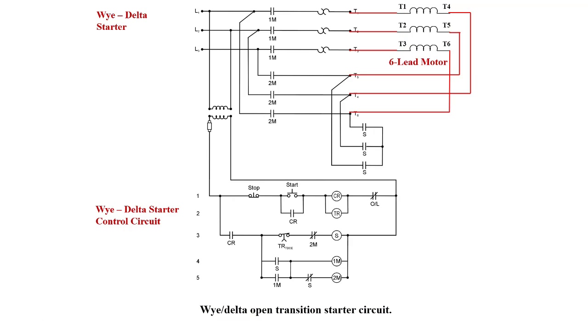Okay, so our Y delta control circuit. Let's have a look how this is going to operate. All right, so we start in the Y connection. I'm going to press the start button right here. What happens? Control relay CR energizes and our timed relay energizes. Control relay CR creates a holding circuit, so CR stays energized, and so does the timing relay. What else does CR do? This normally open contact here closes. It allows current to go through our timed contact, which is a time delay on energization, and normally closed. So current would flow through. 2M is normally closed, so the S coil would energize. Now all S contacts close. So we see S contacts closed.